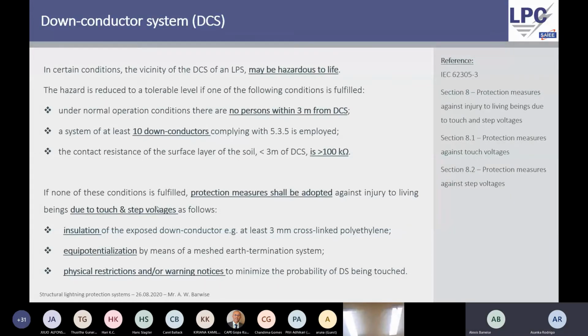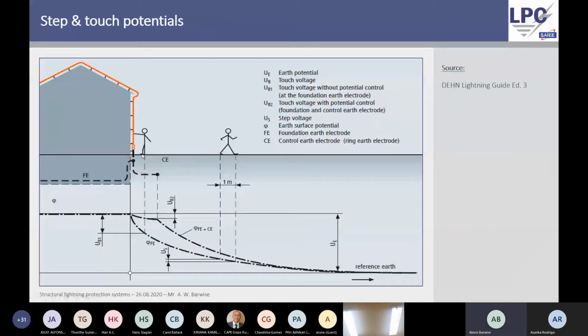If none of these conditions on top are fulfilled, we need to adopt the following possible protection measures. Number one, we have to insulate the exposed down conductors with at least a 3 millimeter thick polyethylene type of conduit. So here I show you the example again. The first was we either lift this human almost into the air with the contact resistance. It's quite often seen inside substations where these stones are used, this crusher stone, because that increases the contact resistance. But otherwise, we have to insulate this down conductor.